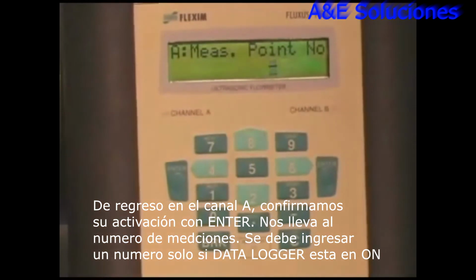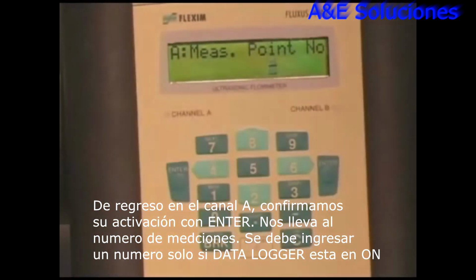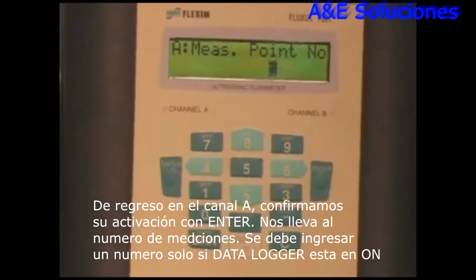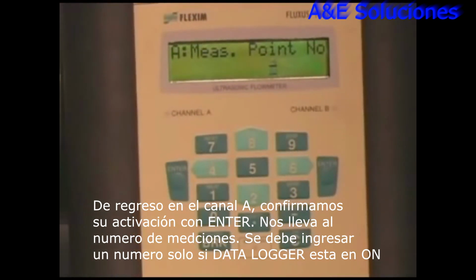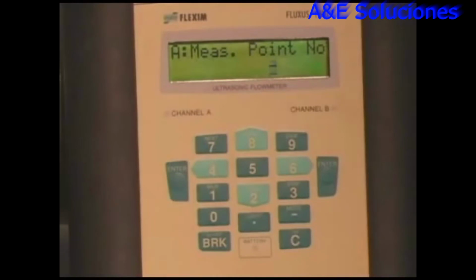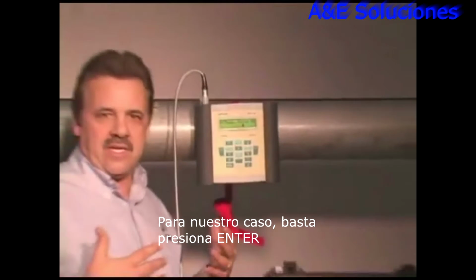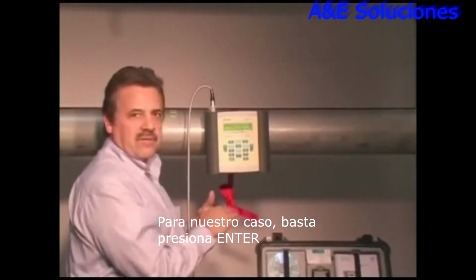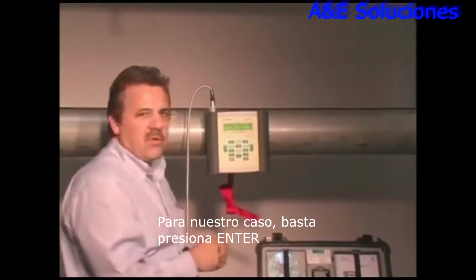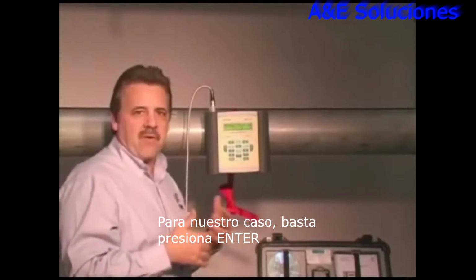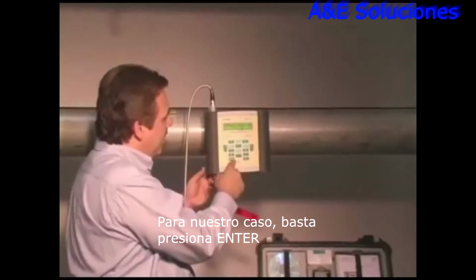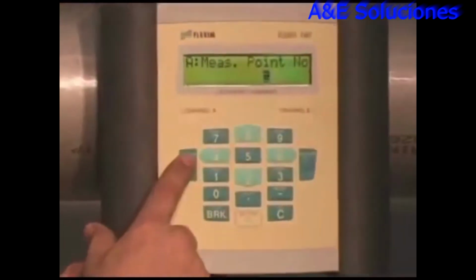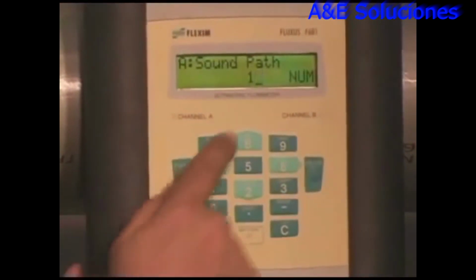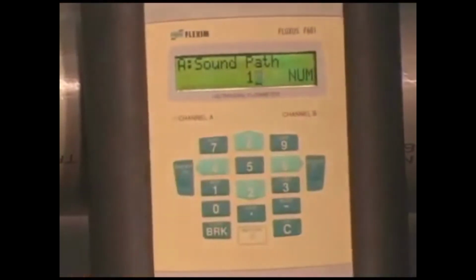It asks a measurement point number. Now, it'll only ask this question if we have our internal data logger turned on. So it happens to be that this data logger is turned on right now, and this measurement point number is just an identifier for what the data set is that we're measuring. And we can choose to put in a number, or we can choose to put in an alphanumeric name or number. Okay, I'll just leave the dash in there. I'll hit enter now. Now it's asking number of sound paths.